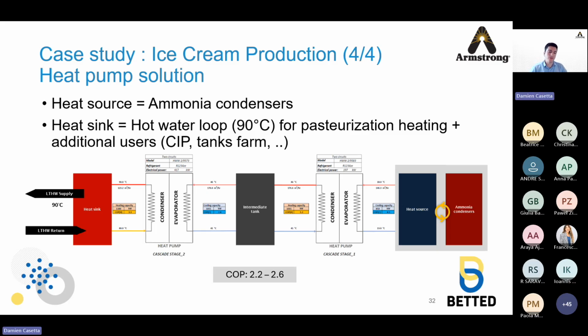And the total efficiency of this case study must account for both the heat pump, but also the direct heat recovery, which comes with an infinite, if I can say, COP. So that's really the combination of both, which would have been dictated by pinch or similar methods, that is defining the system COP, and in the end, the customer OPEX.